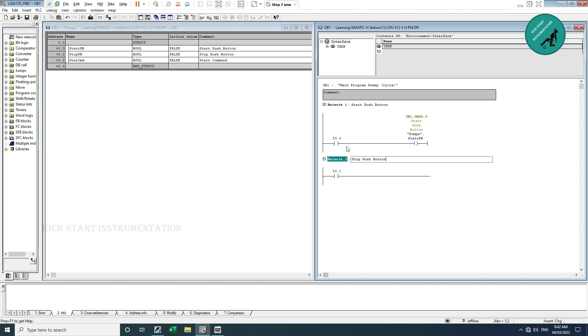What I have done here is mirror the I0.0 address to this particular signal. The reason is that in the program I will be using I0.0 in multiple places. If I want to diagnose, I need not search for I0.0 everywhere. For example, if I need to change I0.0 to I0.2, and I0.0 is used in multiple places in the project, I would have to go everywhere to find and change it.